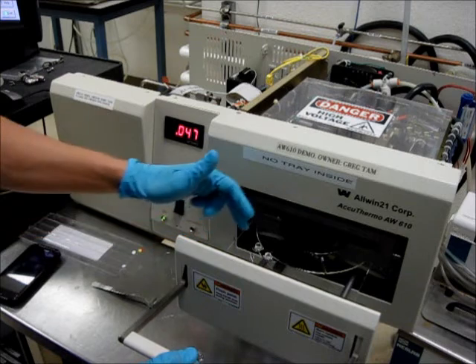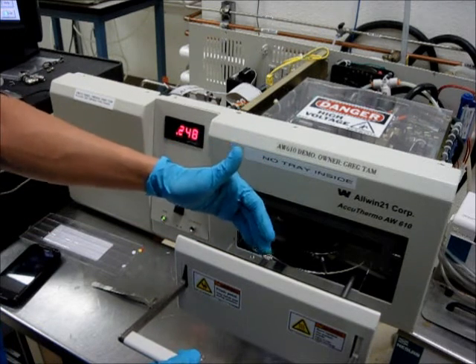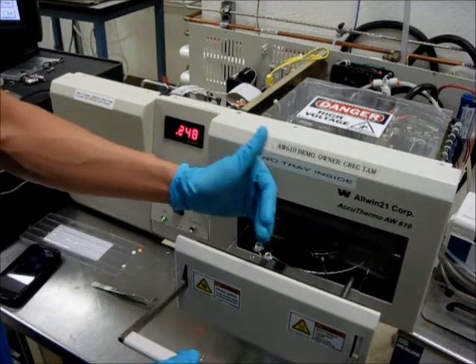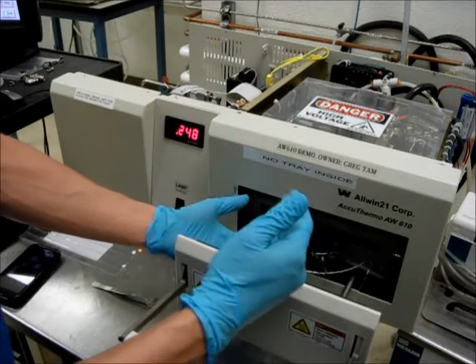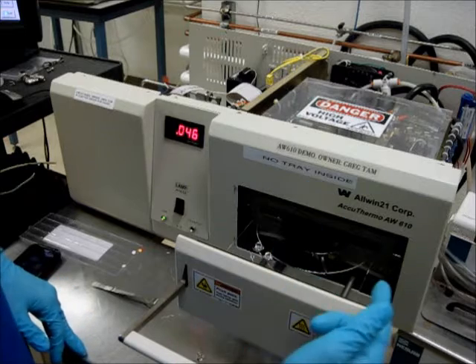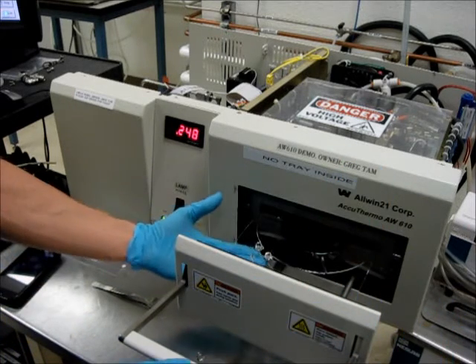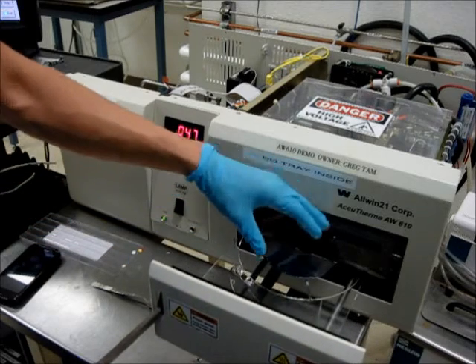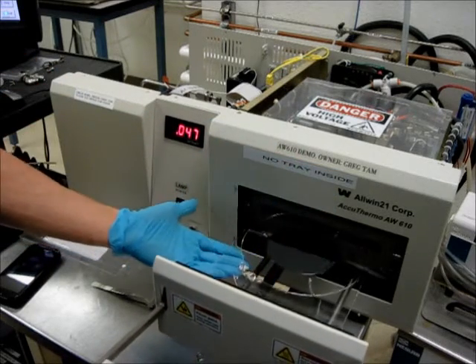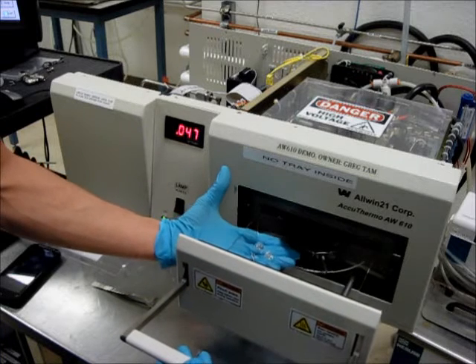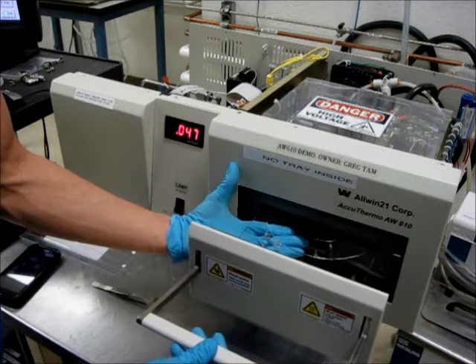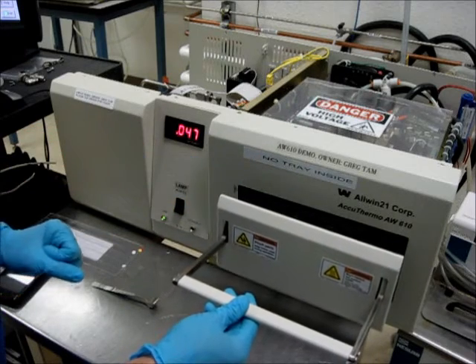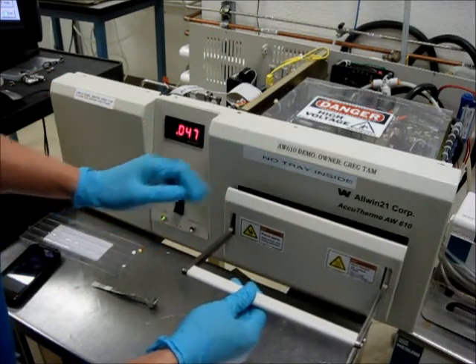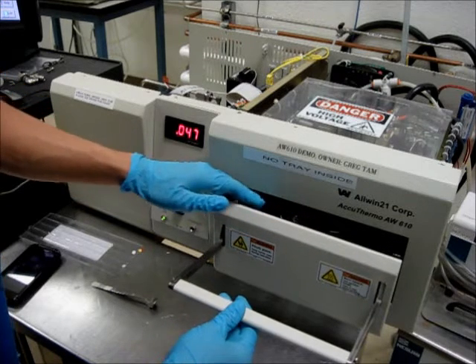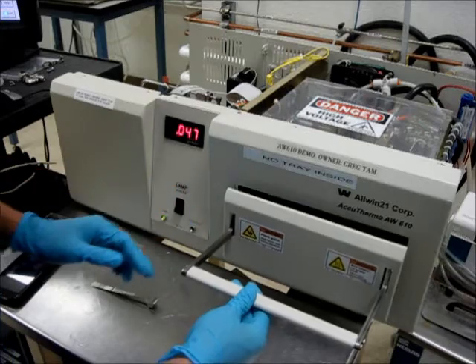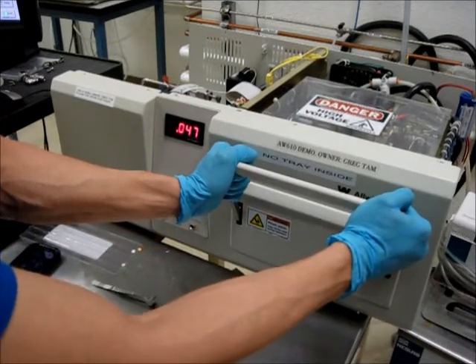Make sure the thermocouple wire that's attracted to the magnet is on the left hand side. The one that's not attracted to the magnet is on the right hand side. When you place the wafer on top of the thermocouple, make sure when you push in the door, the wire doesn't touch the bottom. Close the door.